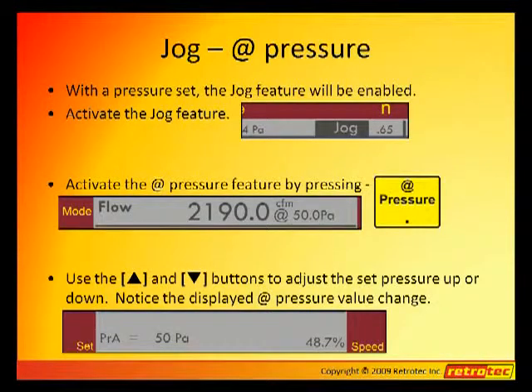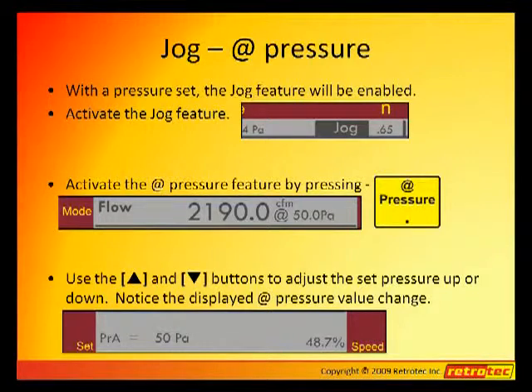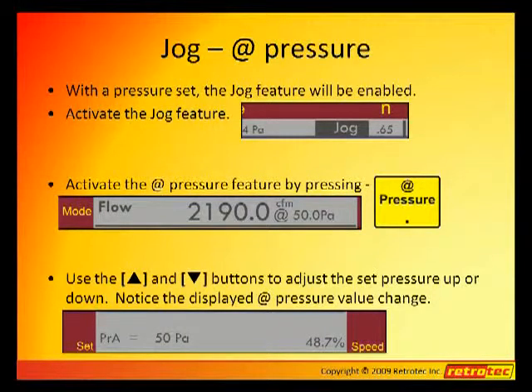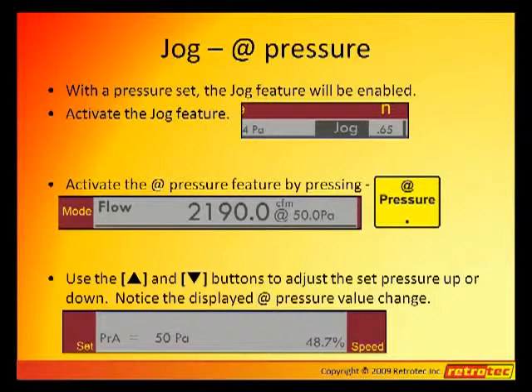Another wonderful feature on the DM2 is to use the Jog feature in conjunction with the At Pressure key. If we press the At key three times, we will cycle around all of the At Pressure settings. One of those At Pressure settings will actually follow the Set Pressure, so if we set pressure to 50, then it will give us the extrapolated pressure to 50 Pa.